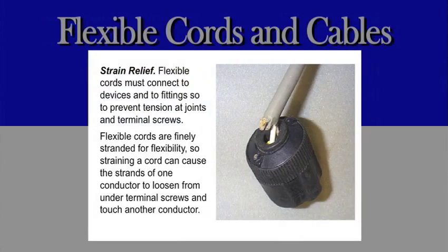Flexible cords must connect to the device and to fittings so as to prevent tension at joints and terminal screws. Flexible cords are finely stranded for flexibility, so straining a cord can cause the strands of one conductor to loosen from the under-terminal screws and touch another conductor.